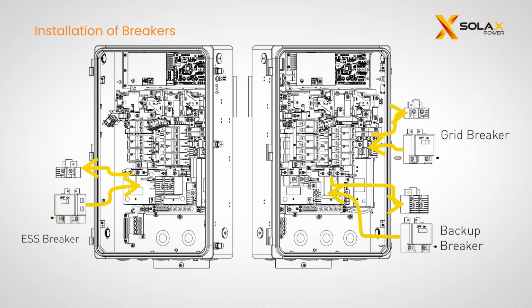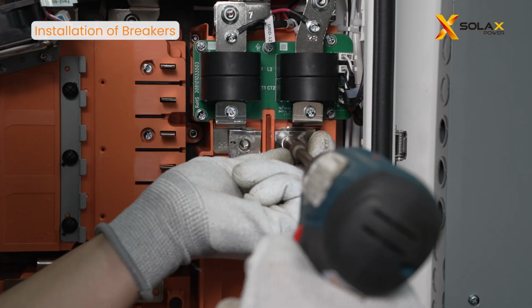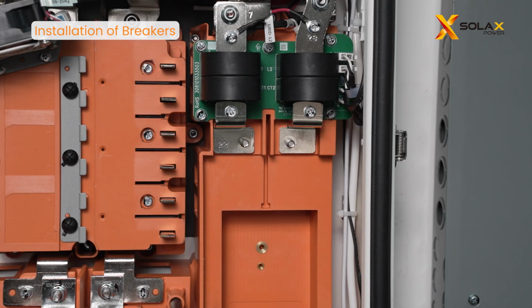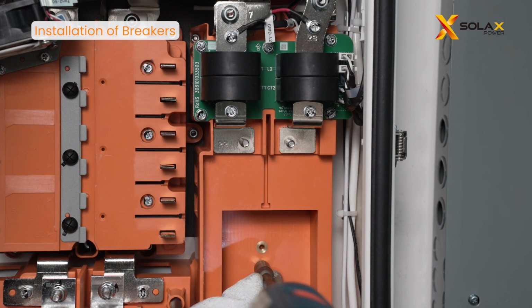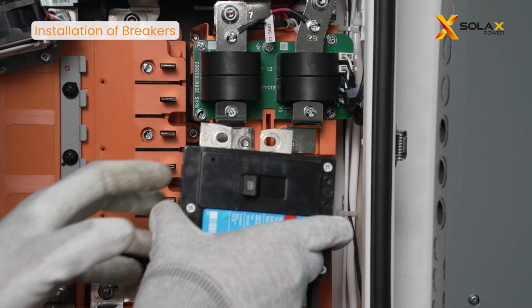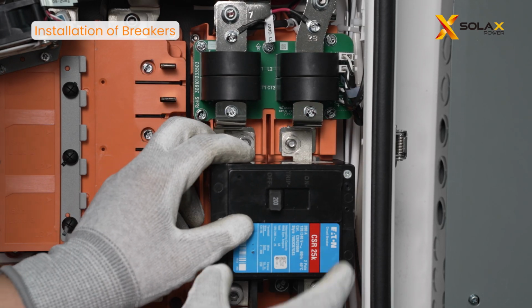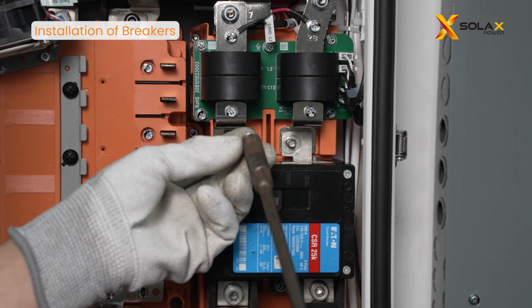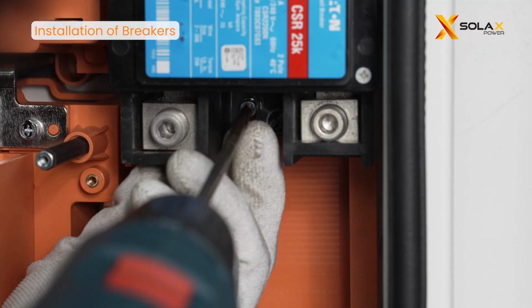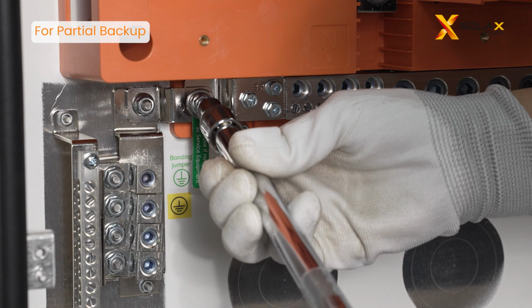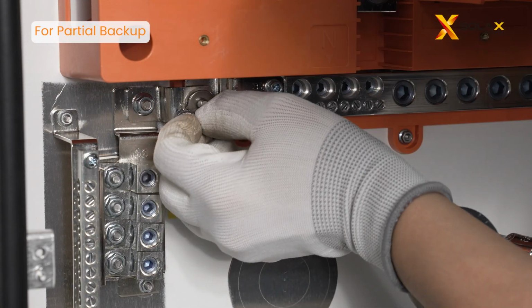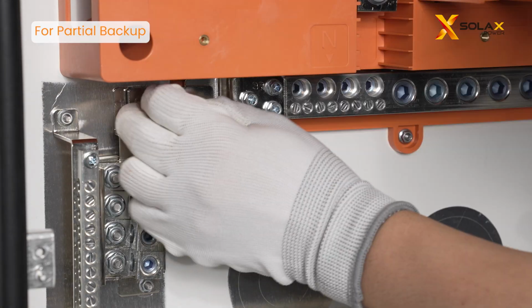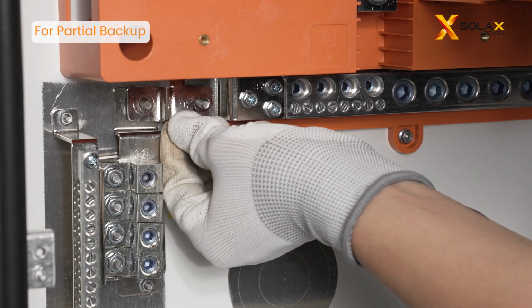The grid breaker has the same installation as the ESS breaker and backup breaker. Here, we take the grid breaker for example. First, loosen the original terminals. Then, install the hexagonal stud. Finally, install the Eaton main breaker and fix it with screws. For subpanel, disconnect the bonding jumper between ground bar and neutral bar. After that, please remember to fix the screws back.